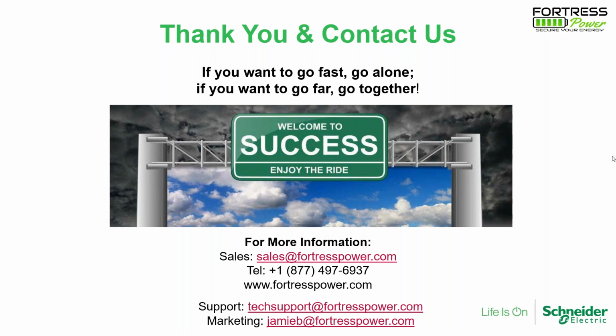Dave is asking what the largest single setup for Fortress batteries is so far. For the eVolt, you can stack up to 12 — that's the system we see. For the eFlex, you can do 15, that's the maximum we allow as a standard offer. If you want to size up bigger on the eFlex, we can do 50 per customized order.